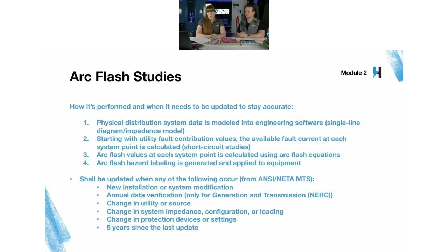Yep. So let's go back and live in that fairyland for a moment. You've changed nothing in your facility. You still need to get your arc flash and your short circuit studies and everything updated every 5 years at a minimum. That's because you don't have control over that utility contribution for the available fault current. Just another thing we can't just blame the utility for. And they don't just give you that information. You have to ask for it. So definitely got to keep that in mind as well. Good question, John.